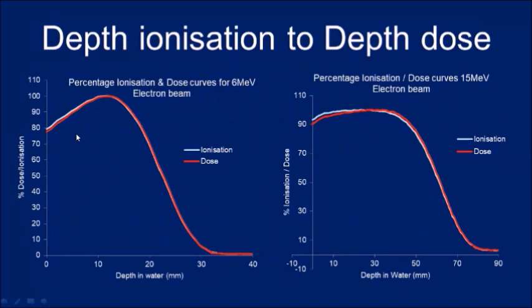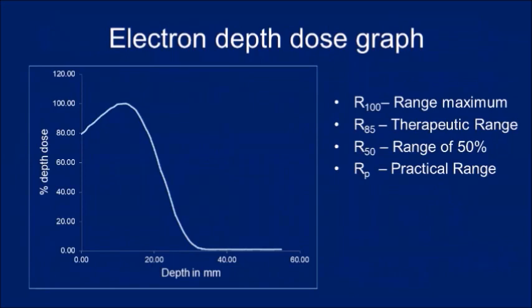For a 6 MeV electron beam, the depth dose curve (red) and depth ionization curve (blue) show a small difference in millimeters, which is nonetheless important. For 15 MeV, the difference between the depth ionization and depth dose curves is more pronounced. When using an ion chamber for depth dose measurement, this conversion must always be taken into account.